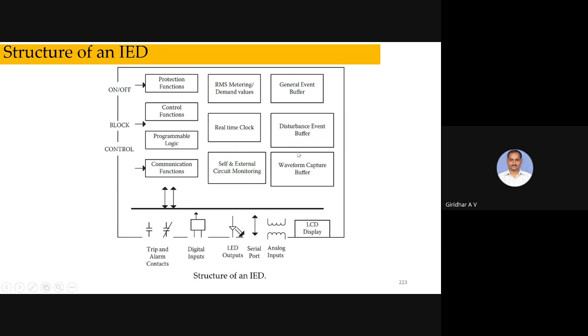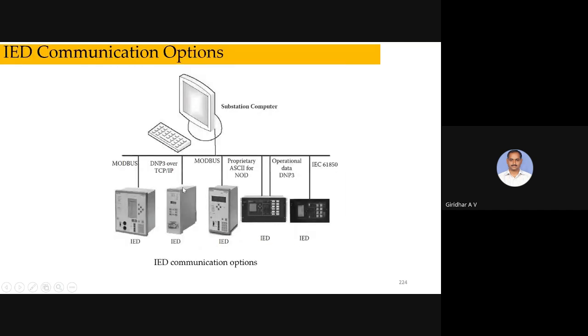So real-time clock, disturbance events, any disturbance will also be recorded. Communication functions, different, as I told, different communication features. Likewise, you can see trip and alarm contacts, digital inputs, LEDs, serial, analog inputs, like that you can get, and it does the processing. So these are typical IED communications. Different communication interfaces it can have, like Modbus, DNP, IEC 61850 through process bus.